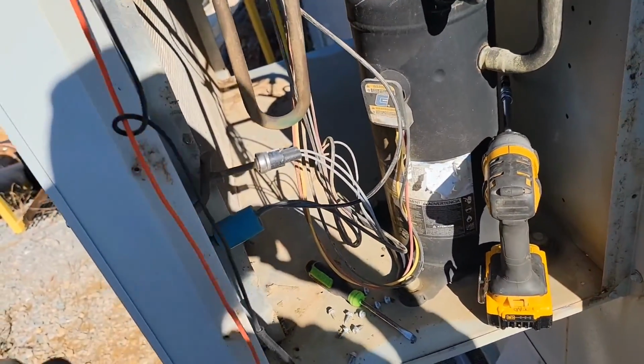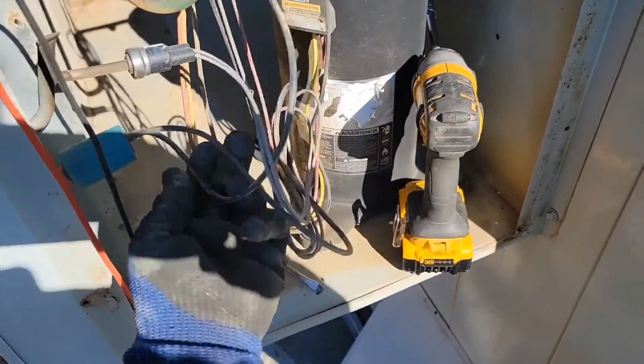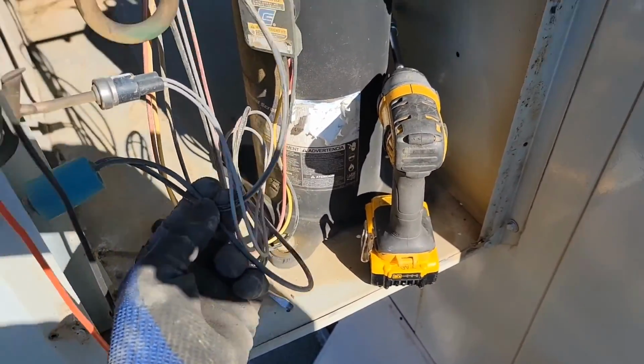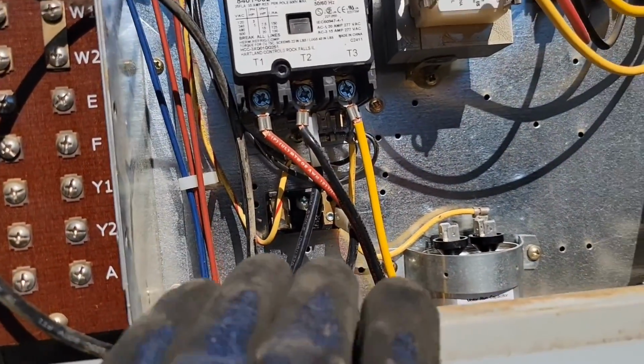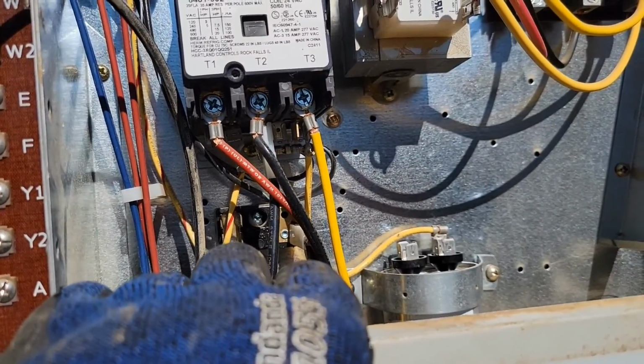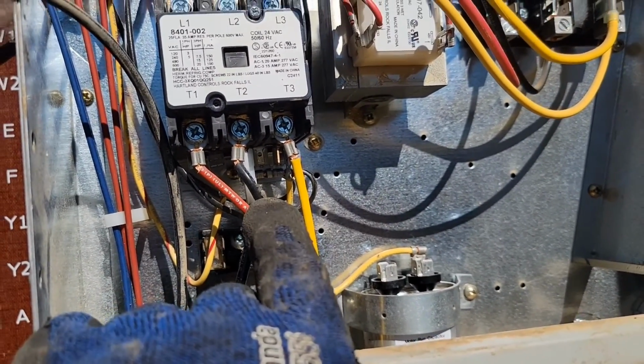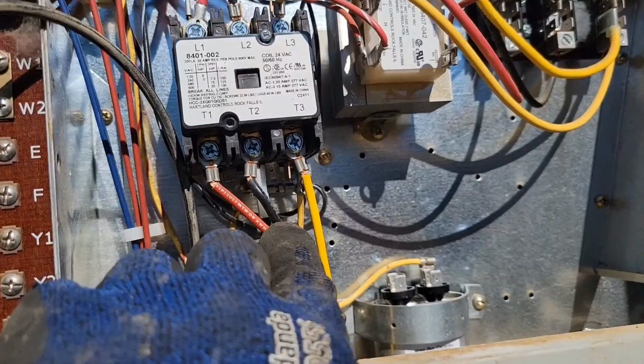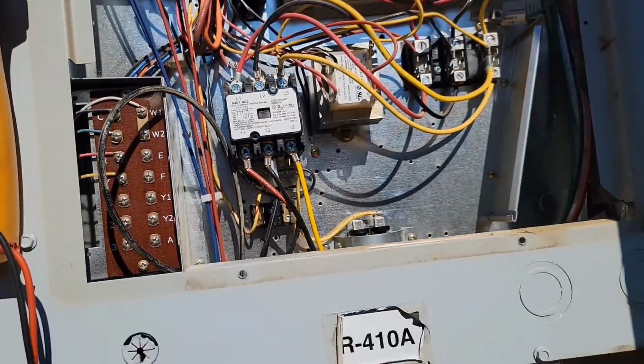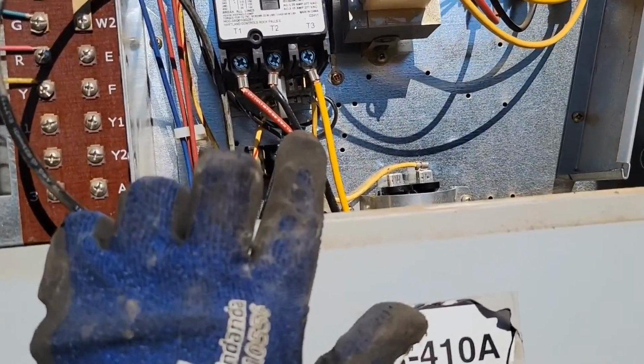So what would I do if the pressure switch was bad? I would turn the breaker off, I would cut the wire here, or I would just take it and connect my fan wire directly to T2. That would be the smarter thing to do. Connect the black wire to T2. That way when the contactor pulls in, you're not going through the pressure switch anymore.